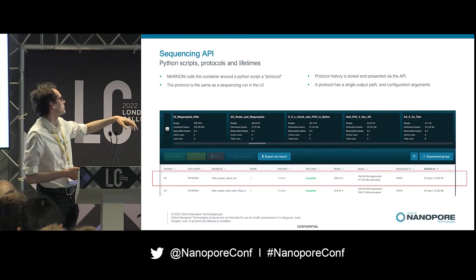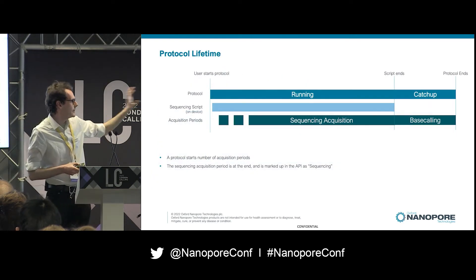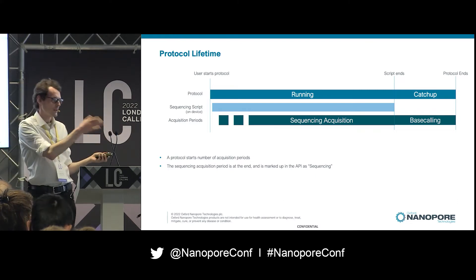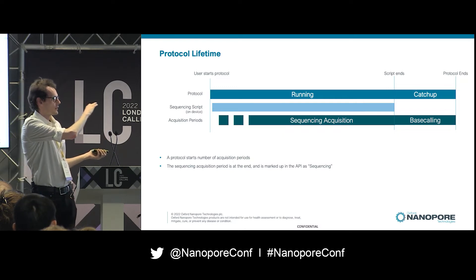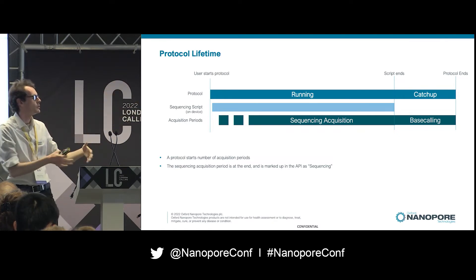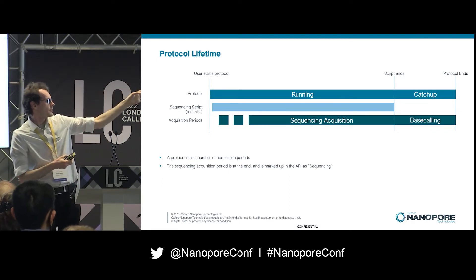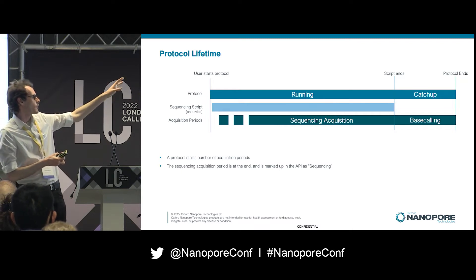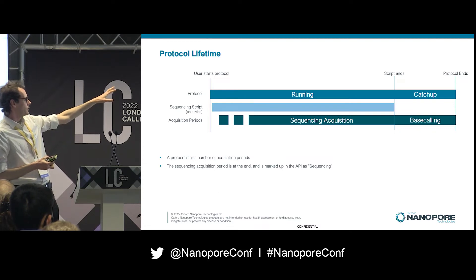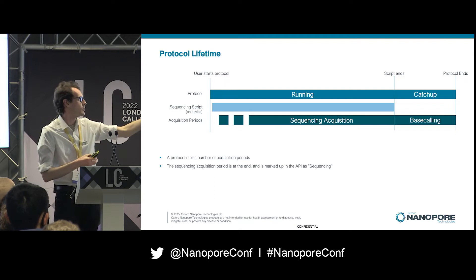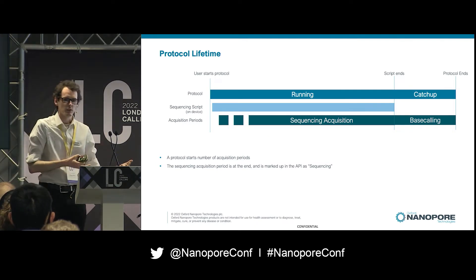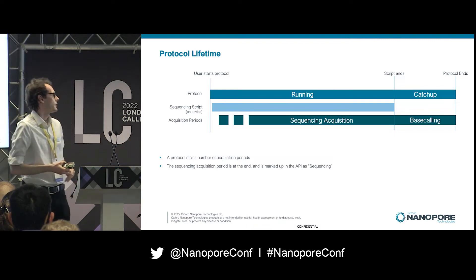You can query back various extra bits about that protocol. Protocols are tied to a Python script — as you start a protocol, MinKNOW kicks off a Python script that does your sequencing, mux scans, and pulls data through your pores. When the Python script ends, if you've got data left to base call, the protocol enters a new phase called catch-up, and we wait for all the pieces your protocol has started to finish before the protocol eventually ends. All the times, the type of sequence script, information about configuration, and the settings you used to start your run — including flow cell ID — are all recorded and stored in your protocol.